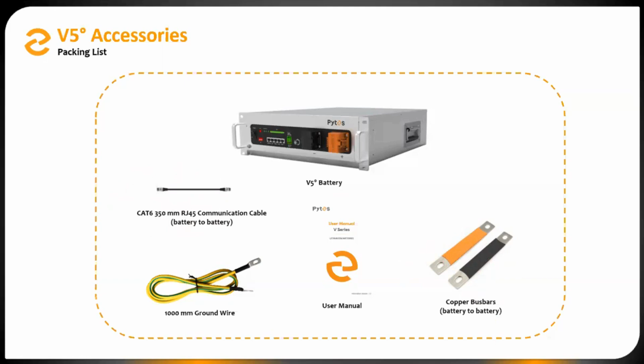The short comms cable and the bus bars only work out if you have the batteries in proximity to each other — either stacked one on top of the other, or with the battery laying on its side like a book on a bookshelf, with neighboring batteries on either side using the bus bars and short comm cables. If you're doing an install where the batteries aren't physically near each other, maybe using custom racking or putting them on a wall, you may not be using the bus bars or included comms cables, but we can help advise on what else would be needed in that case.